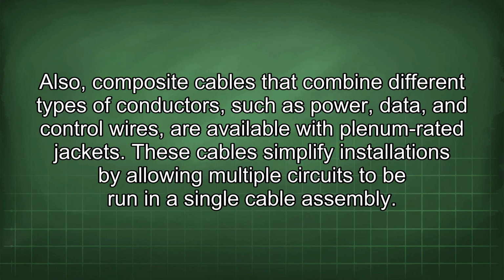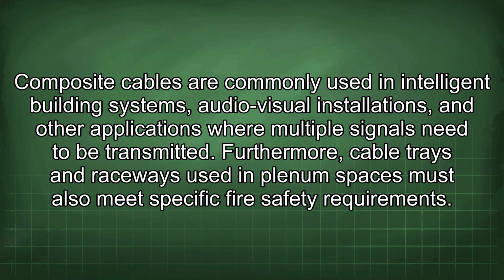Also, composite cables that combine different types of conductors such as power, data, and control wires are available with plenum-rated jackets. These cables simplify installations by allowing multiple circuits to be run in a single cable assembly. Composite cables are commonly used in intelligent building systems, audiovisual installations, and other applications where multiple signals need to be transmitted.